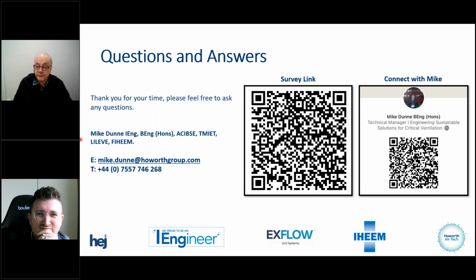Thank you. Somebody else has asked: theatre staff use UCV canopies in setback for conventional operations. Is there anything that should be considered with regards to airflow across the surgical site? Yes. One of the requirements that's always been in HTM, I think it was in the 2007 version, is that when a UCV canopy drops from full speed to setback, from orthopedic to conventional, however you want to word it, when the arrows go from green to amber, we need to achieve between 0.2 and 0.3 meters a second at the bed. Now, the way that it explains it is really sketchy and it's not very clear.